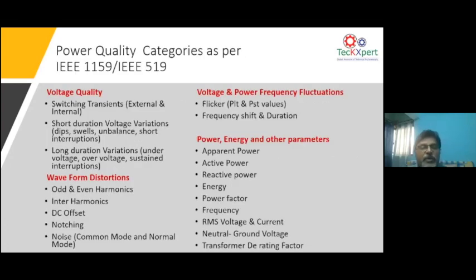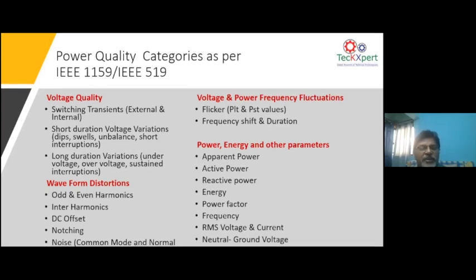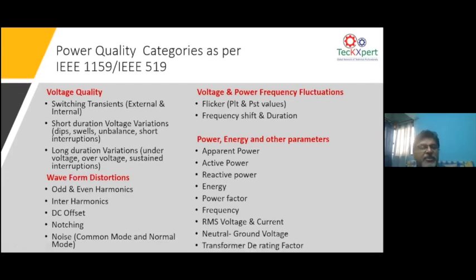As I said before, the characterization of steady state and non-steady state, you can look into fundamentally as voltage quality to start with. When I say voltage quality, it can be affected by switching transients, or it can also be affected by short duration or long duration voltage variation. So when I say switching transients, these are all caused due to lightning, or sometimes capacitor bank switching can also create these transients.